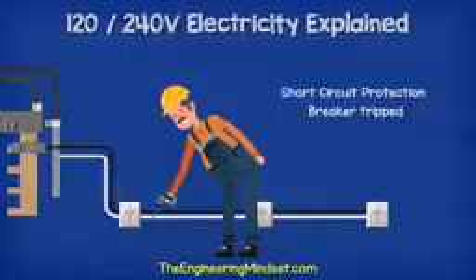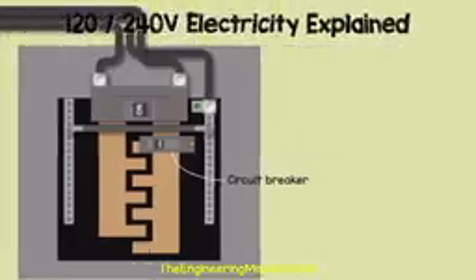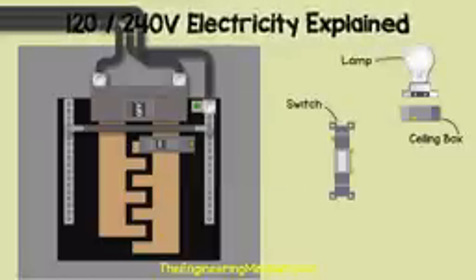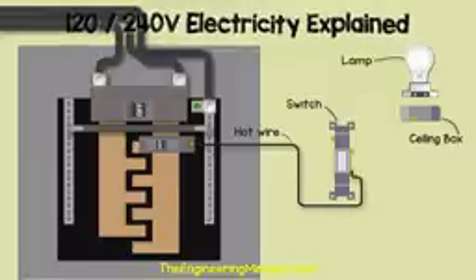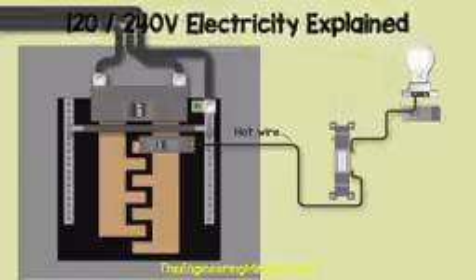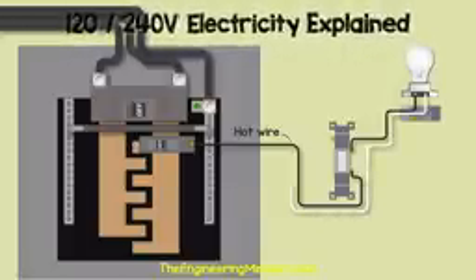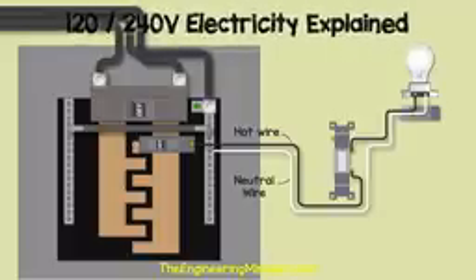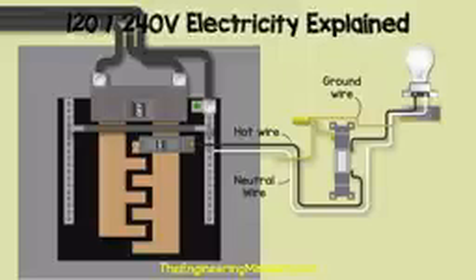Let's have a look at how the circuit breaker is connected to the electrical circuit. In this example, we will connect to a simple light fitting which is controlled by a switch. We take the hot wire from the circuit breaker and run this to the switch. We then run another wire from the switch and over to the light fitting. From the light fitting, we have a neutral wire which carries the return current back to the neutral bus bar. We take the ground wire from the metal casing of the ceiling box and the switch, and we also join this to the neutral bus bar, as in this case it's shared.